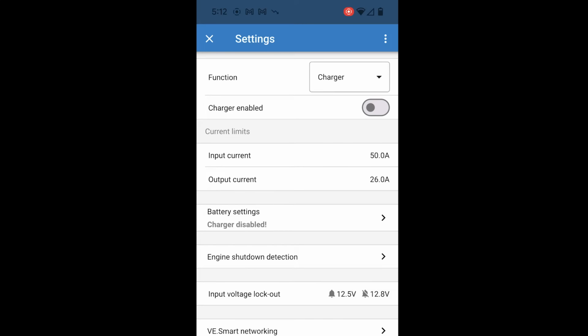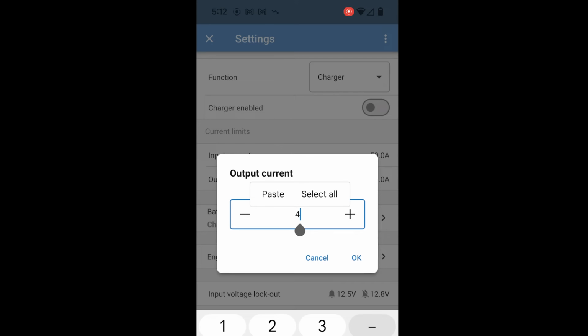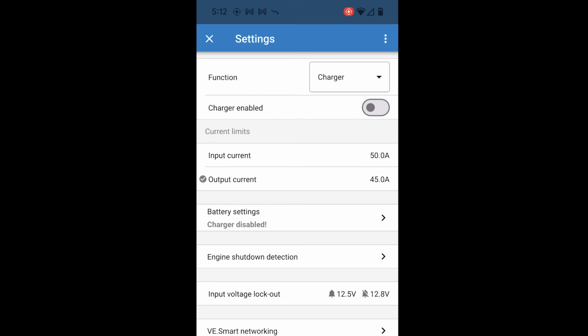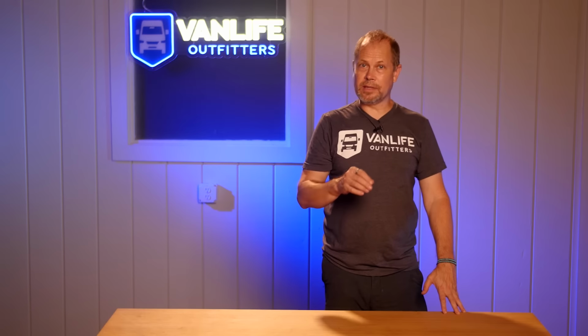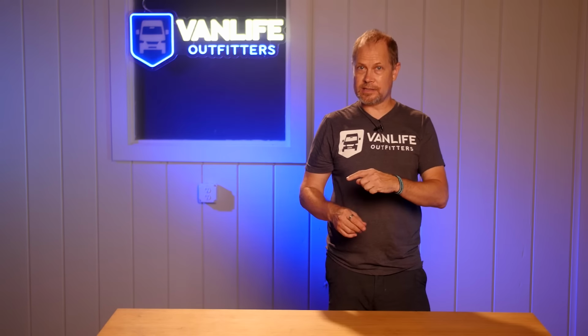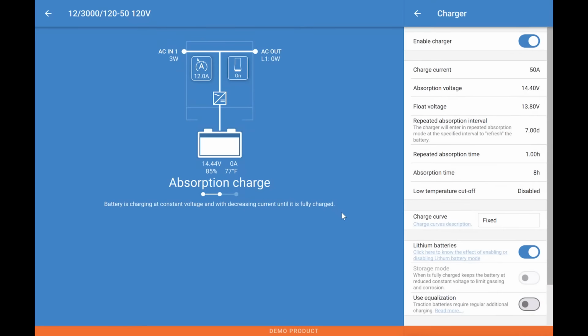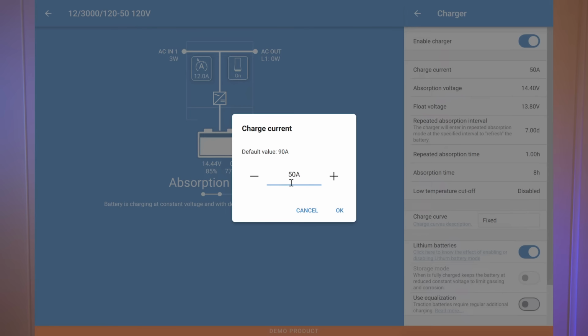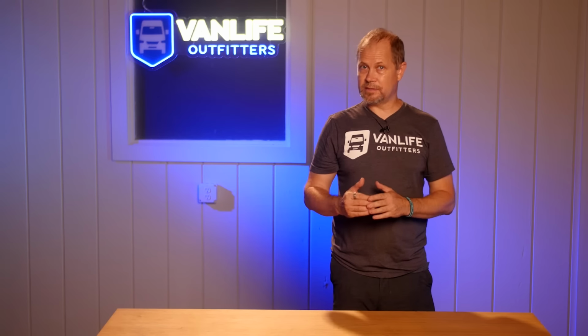Note that the maximum charge currents configured in a device itself using Victron Connect are still in effect with this setting. So in this system, that would be the max charge settings for both the Orion XS and the MultiPlus. But in your system, it could also be another Victron charger like a solar charge controller. As an example, if we were to throttle down the charging capability of the MultiPlus from its maximum of 120 amps to something like 50 amps, which is below the DVCC system-wide maximum currently set to 100 amps, the 50 amps configured at the MultiPlus will be used.